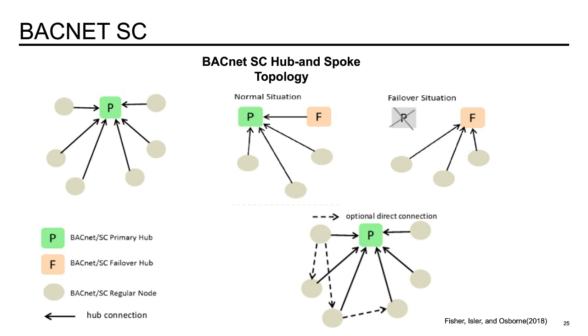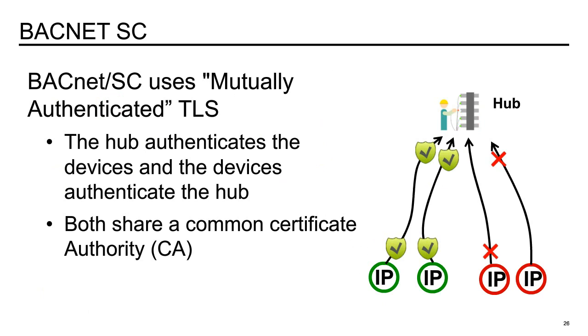So BACnet SC uses mutually authenticated TLS, or transport layer security. The hub authenticates the devices and the devices authenticate the hub, and they both share a common certificate authority. So the TLS protocol provides communication privacy and integrity. The TLS connection between client and server requires one or more of the following. One, a private or secure connection that's based on a shared secret or key from the certificate authority negotiated at the start of the session. Number two, identity of communicating devices is authenticated using public key cryptography. And number three, reliable connection by using a message authentication code to prevent message loss or alteration.